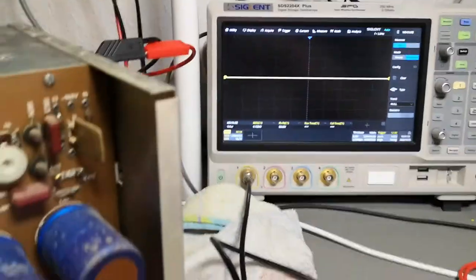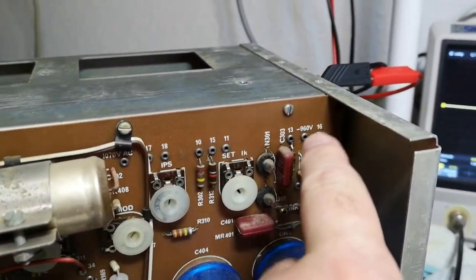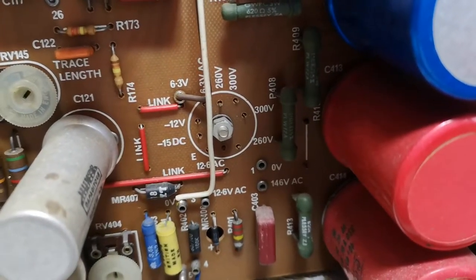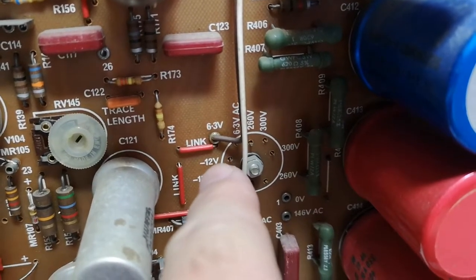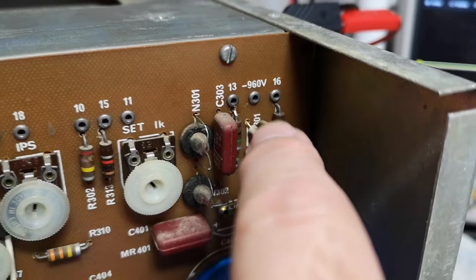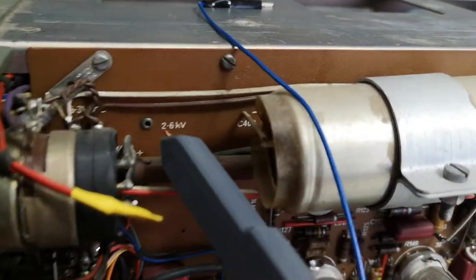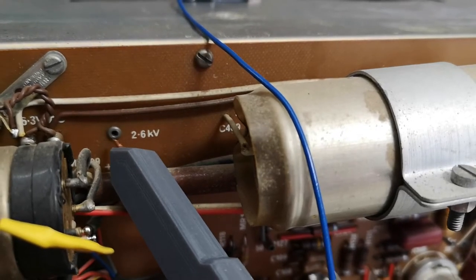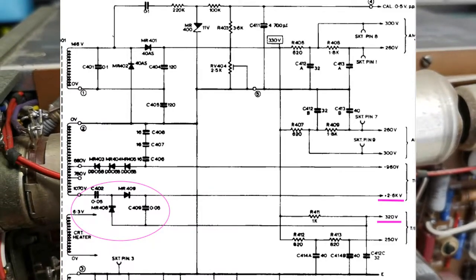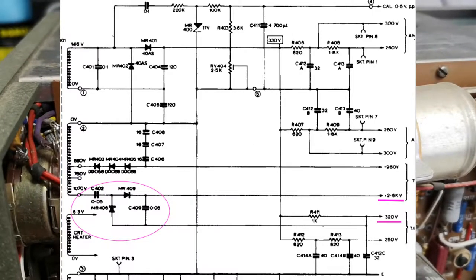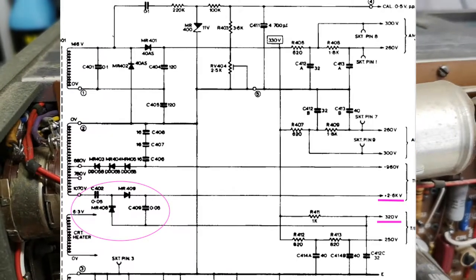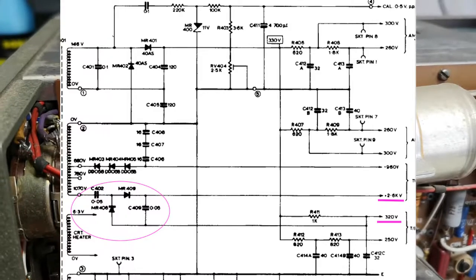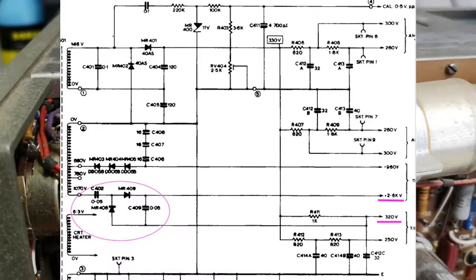I've been measuring a lot of the test point voltages. I am missing minus 12 volts and minus 15 - those are zero volts. Here I got the minus 960 for the cathode stuff, but the anode test point should be 2.6 kilovolts and I measure only 300 volts. Looking at the schematic, the 2.6 kilovolts is made from a voltage doubler connected to 300 volts, so I have a diode that is short circuit or the capacitor is bad.